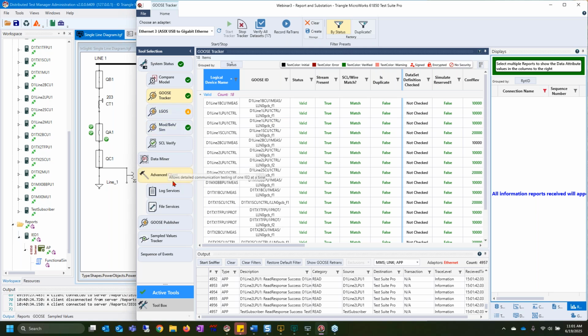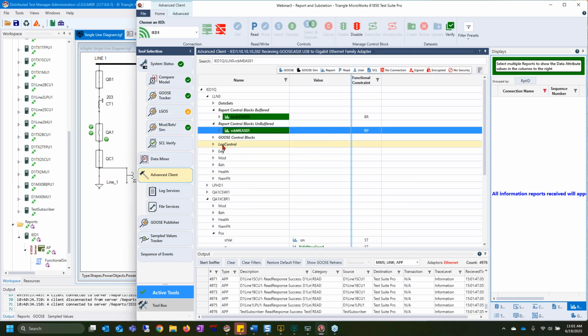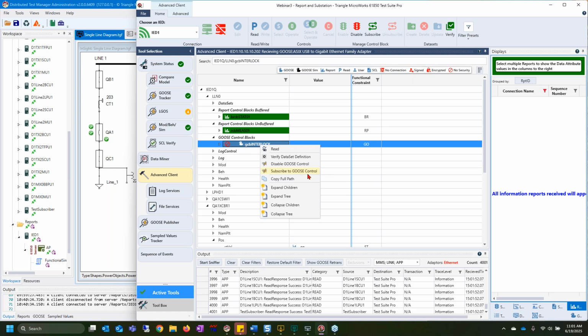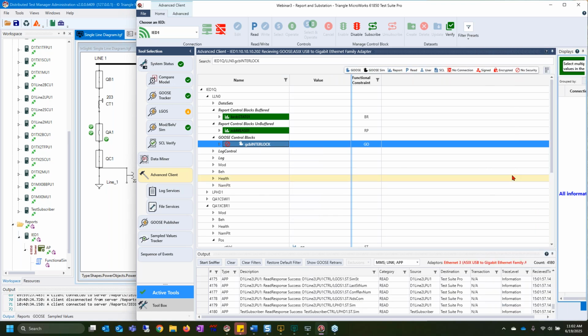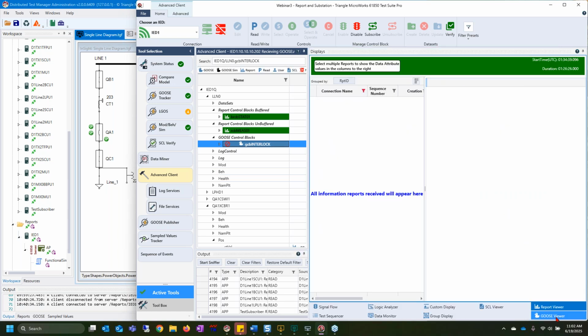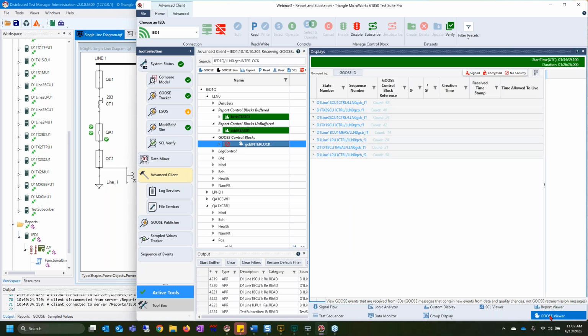Now, in a similar manner to the report viewer, you can actually go over into the advanced client and look at the GOOSE control blocks. So if you right-click on them, you can subscribe to GOOSE. Even though it's typically peer-to-peer, server-to-server, TSP does allow you to subscribe to it through a client. And in a similar manner to the report control block, there's a GOOSE viewer instead of the report viewer.